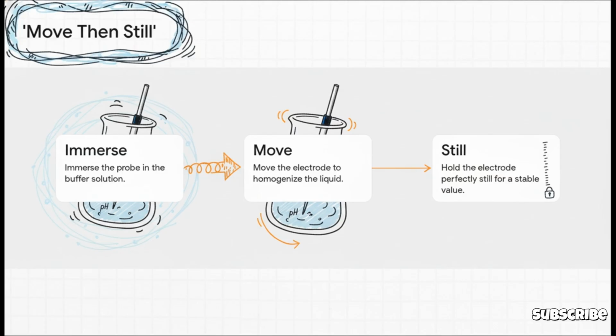Well, when you first put the probe in and give it a little stir, you're making sure the whole surface of that glass bulb gets exposed to a fresh, uniform sample of your buffer. It's like wiping the slate clean. Then you hold it perfectly still. This lets all those ions settle down and properly interact with the gel layer without being all stirred up. It's such a tiny change to your routine, but believe me, you will get faster and way more reliable readings.